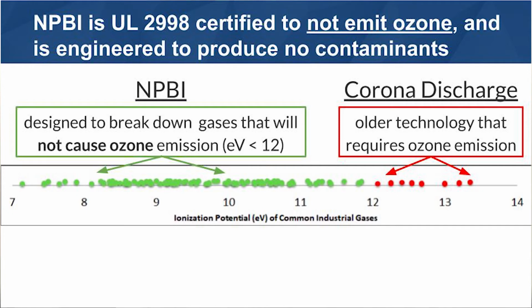And when you ionize oxygen, you always get ozone as a byproduct. Now, while you can try to limit the amount of ozone with those types of systems by controlling the voltage to just the point where the tube's conducting, it still generates that corona discharge, which is going to generate ozone as a byproduct. And so the way to prove the systems are safe and effective, regardless if you're talking about Global Plasma Solutions or our competition, is ask for their UL 2998 certification. I don't know of any manufacturer that makes glass tubes that could possibly pass that, based on my experience. I came from that industry. I have personal experience, and I don't know of any system or any method you could possibly use to produce ions with a glass tube system or a composite tube system without the formation of ozone as a byproduct that would still be below that 5 parts per billion threshold.